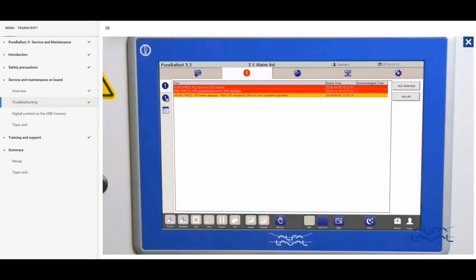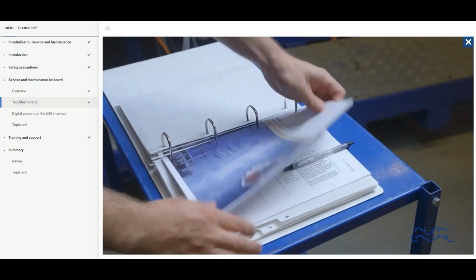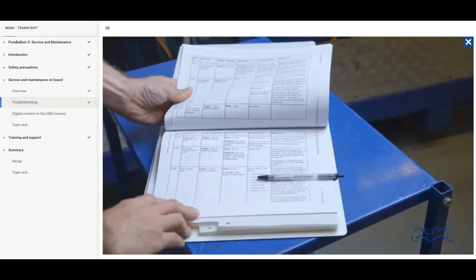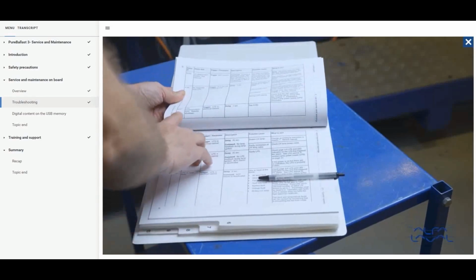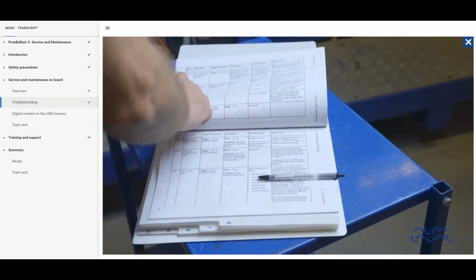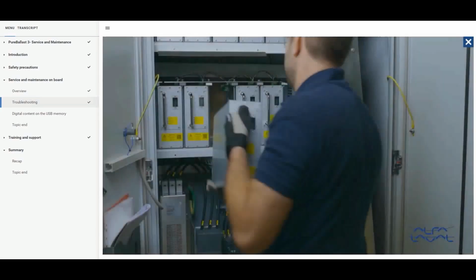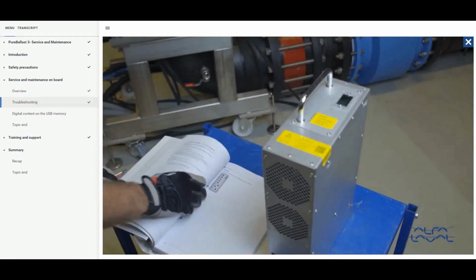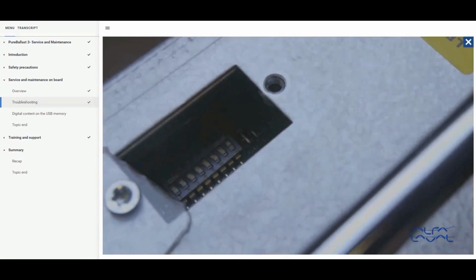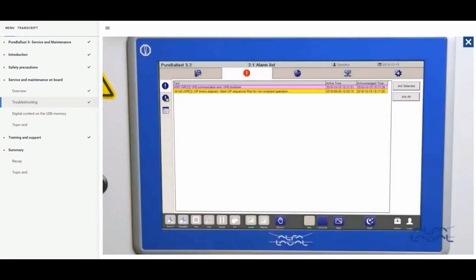To troubleshoot the alarms, start by pressing Ack All to acknowledge the alarms. Only the active alarms will remain, and they will change color to indicate that they are acknowledged, but still active. See the System Manual for detailed information about alarms and how to troubleshoot them. Troubleshoot one cause at a time. Press Ack All to see if the problem is resolved.